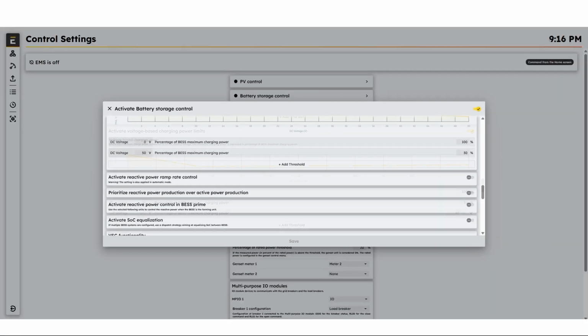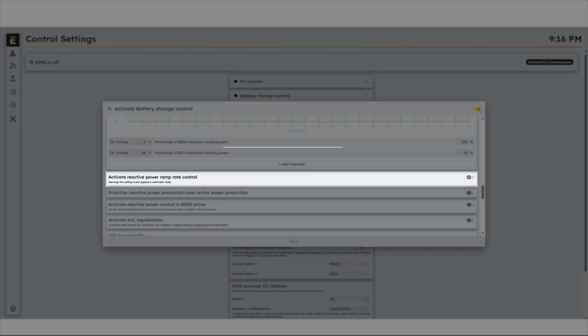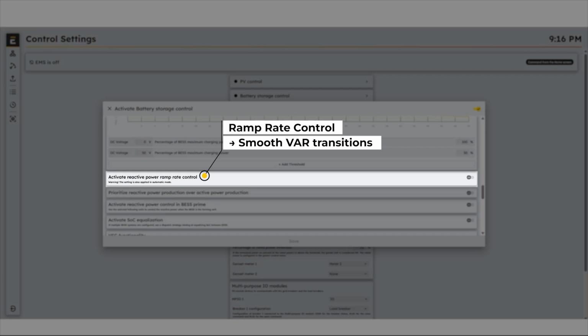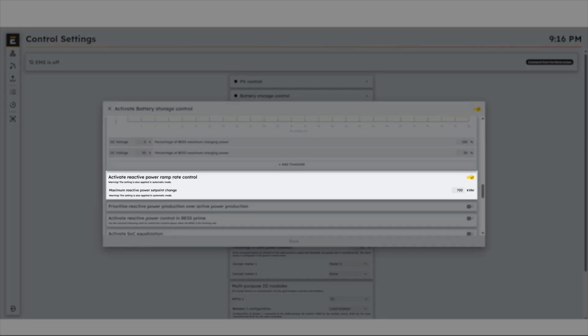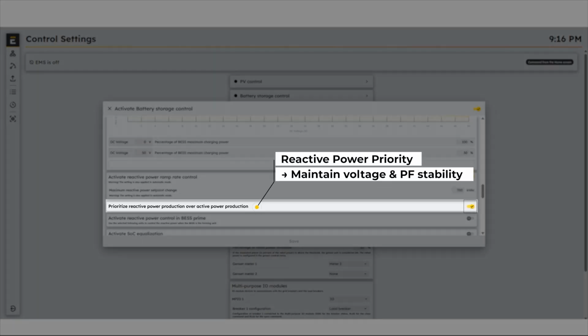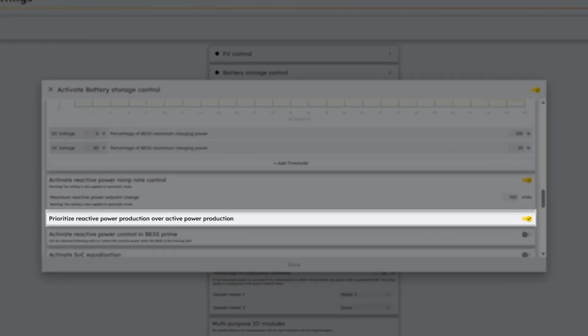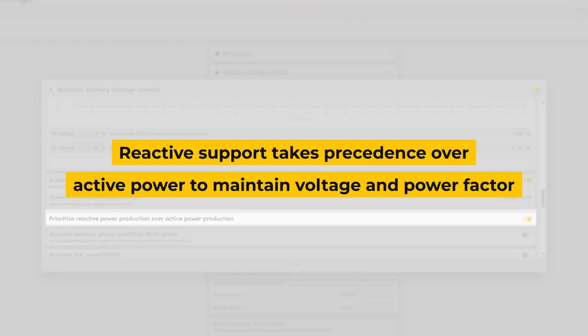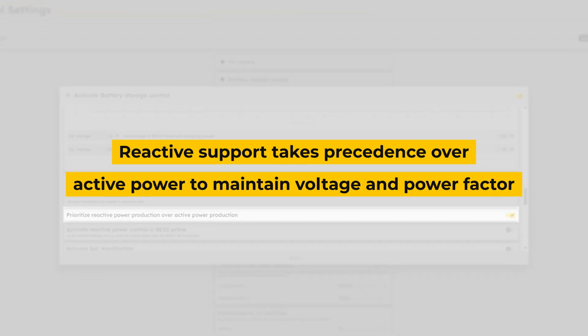This section manages how the EMS regulates and prioritizes reactive power when operating in grid mode. The reactive power ramp rate control smooths transitions in VAR output by limiting how fast VAR set points can change, ensuring voltage stability and avoiding abrupt grid fluctuations. When reactive power priority is enabled, the EMS gives precedence to reactive power delivery before active power, maintaining the desired voltage and power factor even during grid events or dynamic load variation.